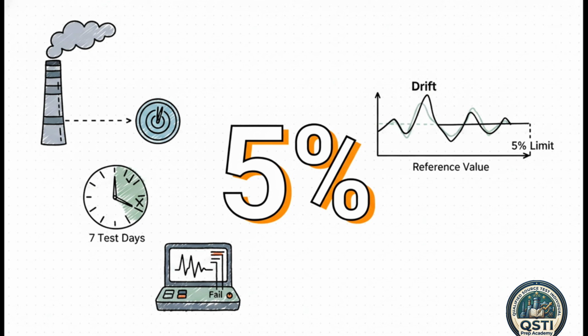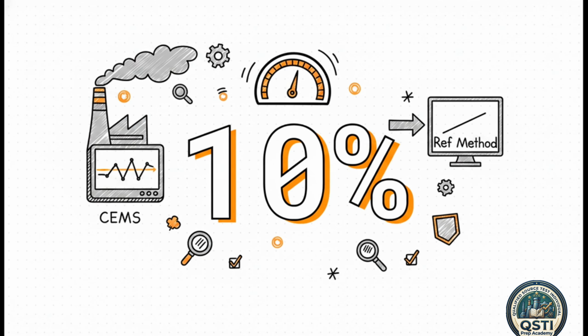That's a really fascinating detail, right? Requiring it for 6 out of 7 days actually acknowledges the messy reality of industrial equipment. It allows for one potential anomaly, but it still relentlessly demands consistent overall precision. If it drifts more than 5% from the established span value on multiple days, boom, it fails the lie detector test outright, no exceptions.